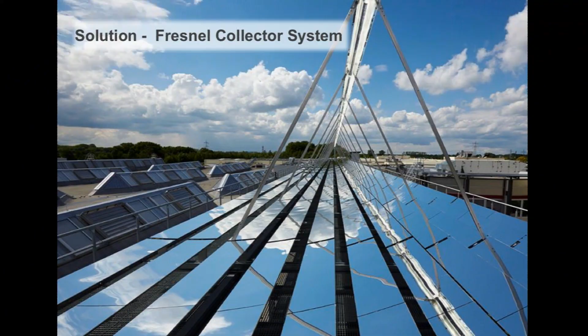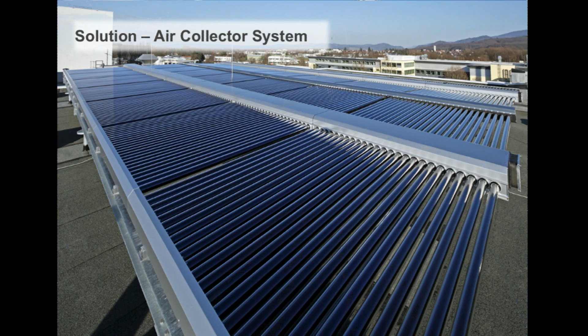That's an example installation in Germany. This is a string about 80 to 84 meters long, used with pressurized water for driving an absorption chiller. Here you can nicely see the primary mirrors, and on top is the receiver with the vacuum receiver and secondary mirror. You can already see the advantage - with the Fresnel collector, you can go on rooftops. It has very low wind resistance, and the mirrors are very close to the ground or rooftop.